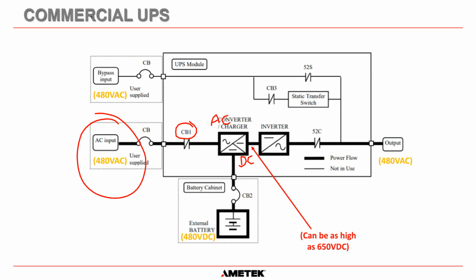What they have is a charger that trickle charges the battery, and there's also a DC to DC converter inside this section here. Okay, and then it also has a diode bridge. So this charger isn't a control bridge. It would just have 6 diodes, and it will convert whatever that 480 volts going in into DC, which usually works out to about 600 volts DC. Okay, it doesn't change. That's just the DC that goes into the inverter, and the batteries are usually charged at a nominal 480 volts for this system. So the DC bus is very high in this system.